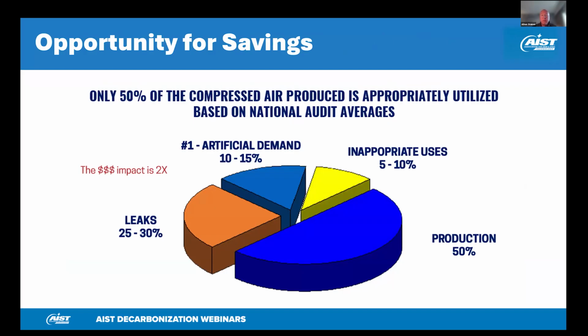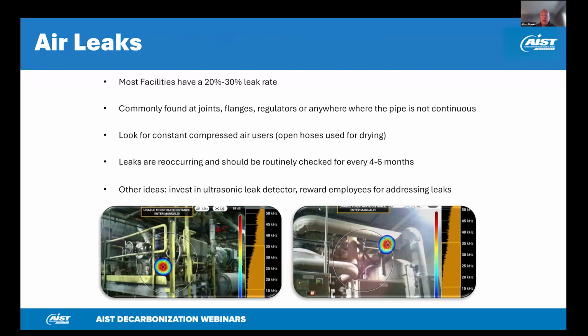As we discussed earlier, 50% of all the compressed air that is produced goes to waste. And it really falls into 3 buckets: inappropriate uses, artificial demand, and leaks. We're going to talk about each one of those for a minute. Air leaks, that's the favorite child to talk about. They're easy to identify. They typically make up 20 to 30% of the total compressed air consumption in a plant. Most of these are found at the point of use where your joints and flanges go down to a regulator or hoses or tubing, polytubing, and it's really inside the machine or near the application of the air.